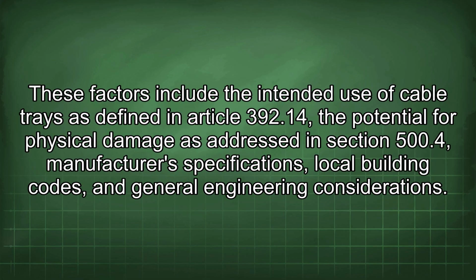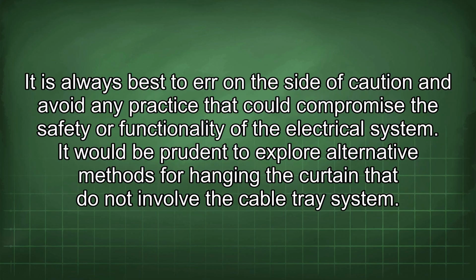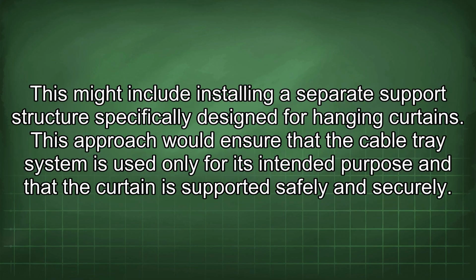These factors include the intended use of cable trays as defined in Article 392.14, the potential for physical damage addressed in Section 500.4, manufacturer specifications, local building codes, and general engineering considerations. It is always best to err on the side of caution and avoid any practice that could compromise the safety or functionality of the electrical system. It would be prudent to explore alternative methods for hanging the curtain that do not involve the cable tray system. This might include installing a separate support structure specifically designed for hanging curtains. This approach would ensure that the cable tray system is used only for its intended purpose and that the curtain is supported safely and securely.